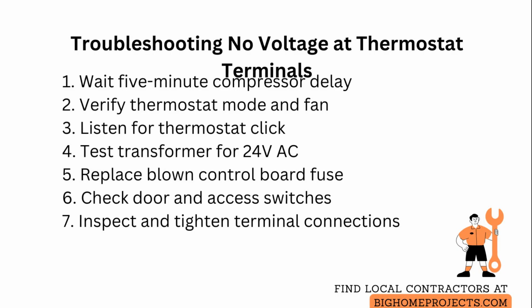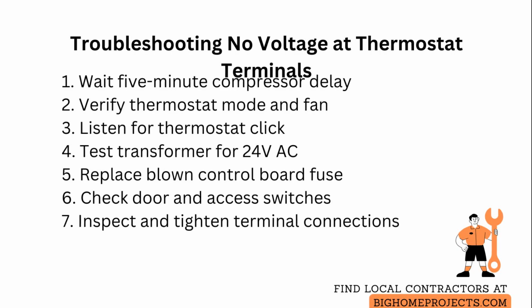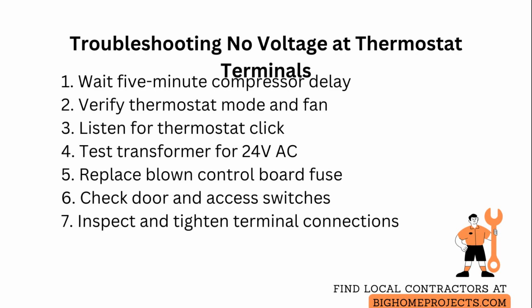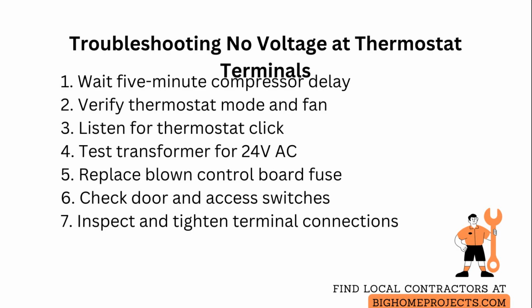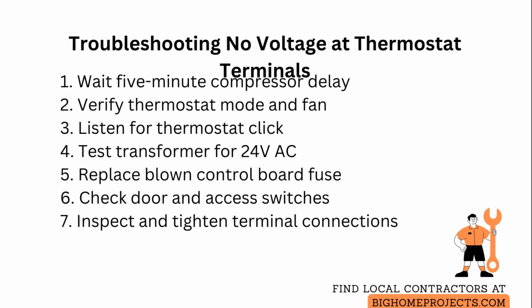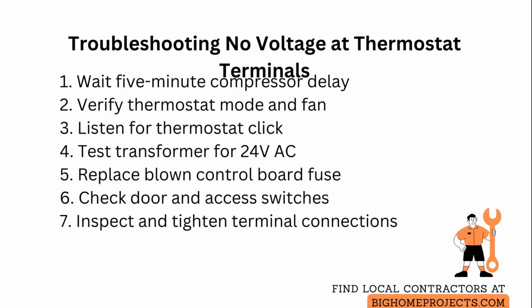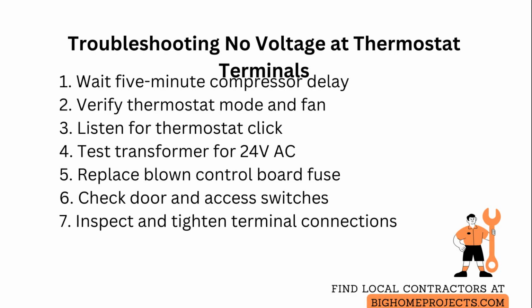Test the transformer secondary at its terminals with a multimeter to confirm the presence of the required 24-volt alternating current. If the transformer is open or the fuse on the control board is blown, replace the fuse or transformer as specified by the equipment manual. Check for an open door or access panel switch on the furnace or air handler, which will interrupt control circuits and show 0 volts at remote terminals until the panel is properly seated.